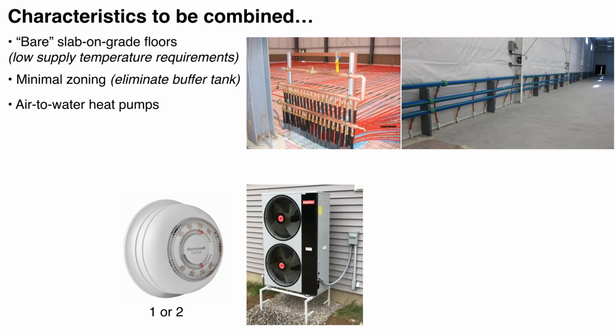Again, we're going to bring air to water heat pumps in, not only as our primary heat source, but also as potential to produce chilled water and add cooling. And many of these buildings, at least in the northern climates, in the past don't have cooling. And it's a nice upsell, especially with bringing the air to water heat pump in. You have the ability to do this. You're in effect buying a chiller when you buy an air to water heat pump. It's just a matter of how I detail out the distribution system to use that chilled water.